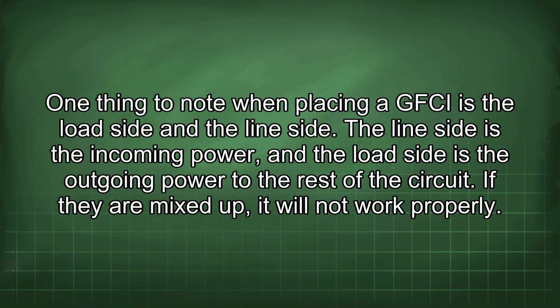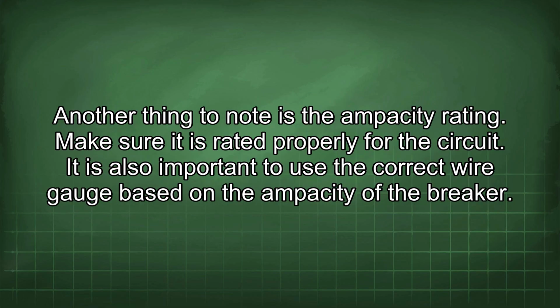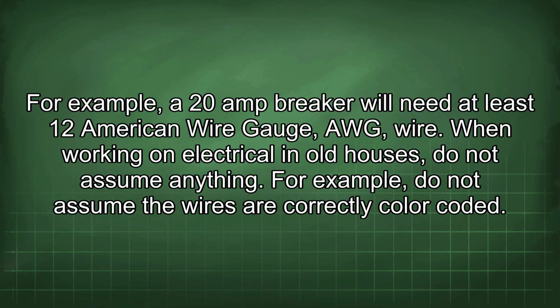The line side is the incoming power, and the load side is the outgoing power to the rest of the circuit. If they are mixed up, it will not work properly. Another thing to note is the ampacity rating. Make sure it is rated properly for the circuit. It is also important to use the correct wire gauge based on the ampacity of the breaker. For example, a 20 amp breaker will need at least 12 American wire gauge (AWG) wire.